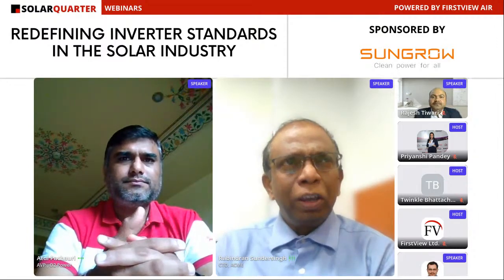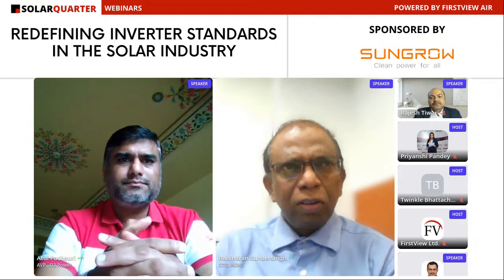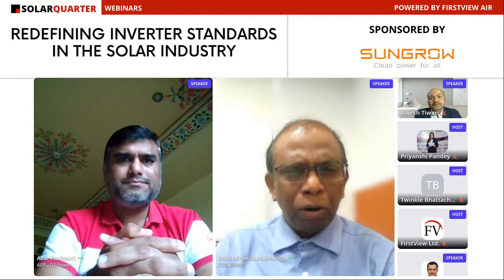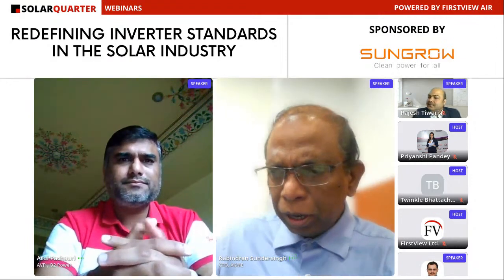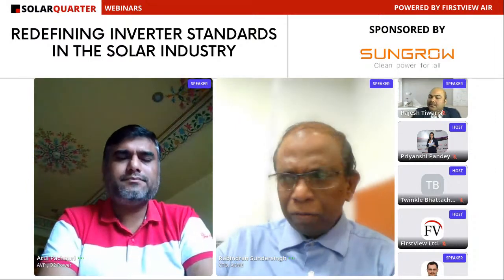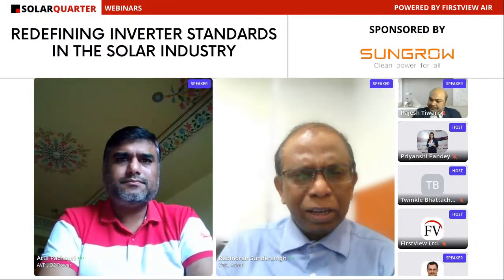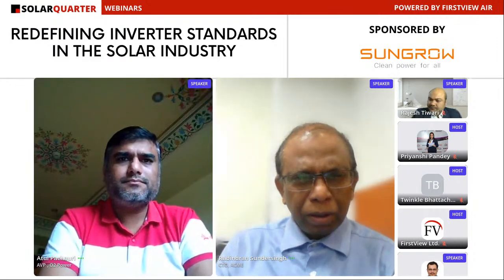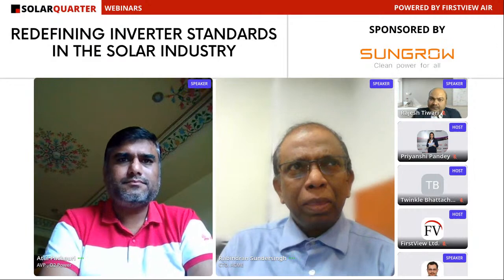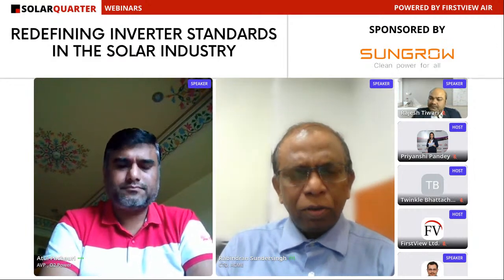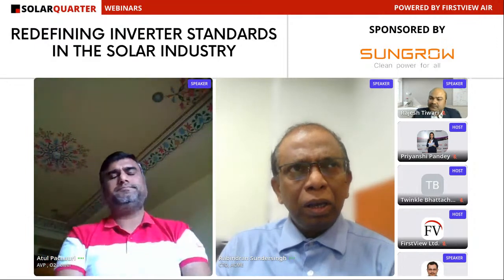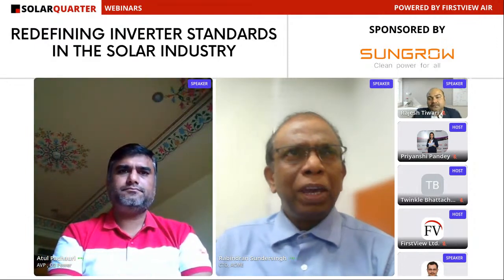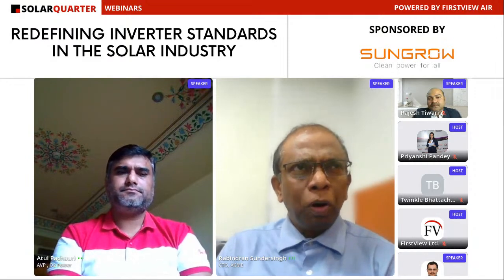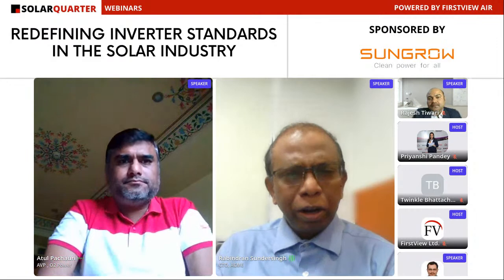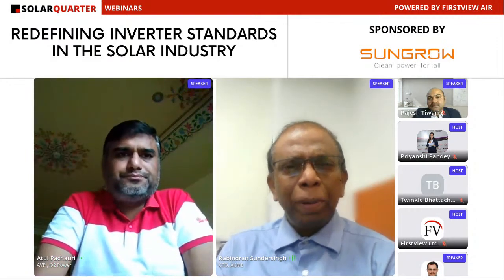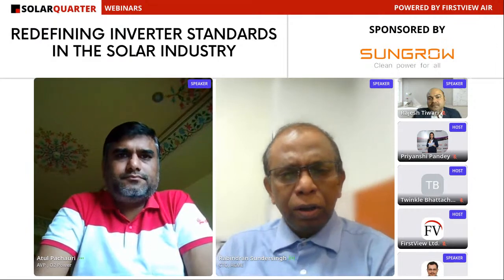But on the grid side, there's a lot of new requirements I'd like to talk about. One is the steady state behavior mandated by the CEA technical standards for connectivity to the grid. Though the requirements are a little vague and not very well spelled out, the underlying interpretation is that you have to be capable of responding with reactive power as and when the grid demands, to the extent of one third of your capacity, equivalent of 0.95, and so on.